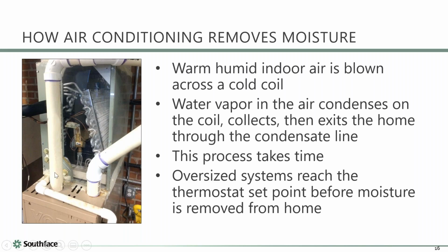Yeah, and the point too is that it probably takes about 15 minutes for this to hit steady state. And until liquid water physically leaves out this pipe, you really have not done any dehumidification, because the moisture, if it's still on the coil, will just re-evaporate. And if you left your fan running all the time, it would really re-evaporate. So we don't typically recommend that you do that unless there's some other reason.